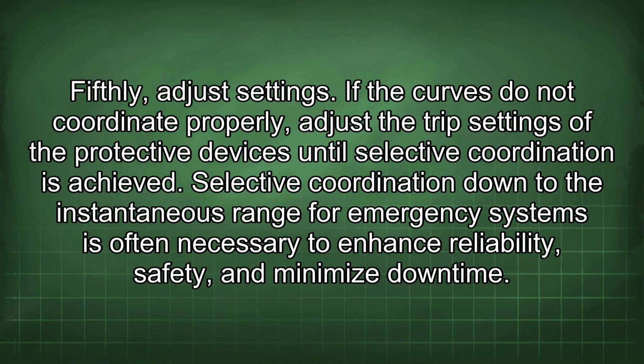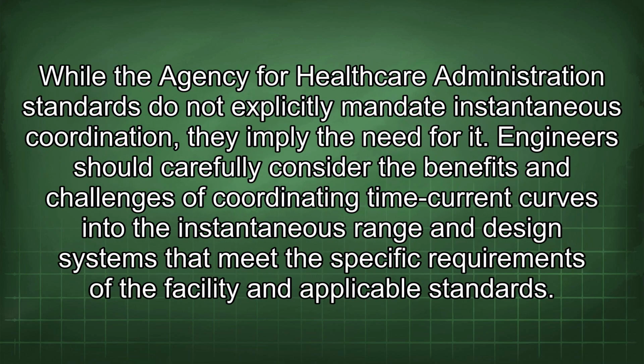coordination is achieved. Selective coordination down to the instantaneous range for emergency systems is often necessary to enhance reliability, safety, and minimize downtime. While the Agency for Healthcare Administration standards do not explicitly mandate instantaneous coordination, they imply the need for it. Engineers should carefully consider the benefits and challenges of coordinating time current curves into the instantaneous range and design systems that meet the specific requirements of the facility and applicable standards.